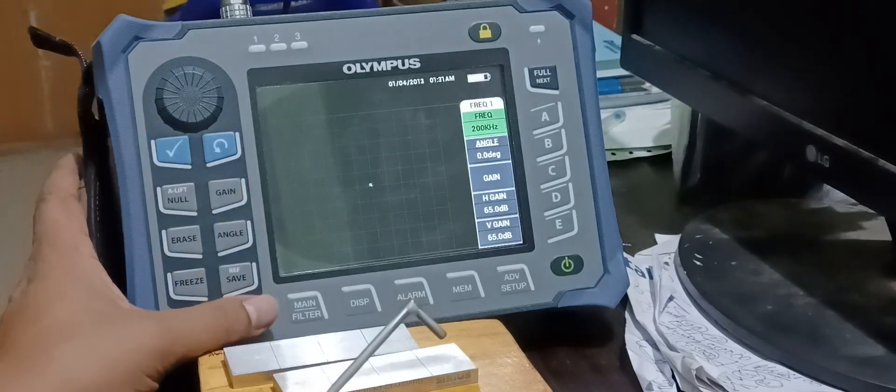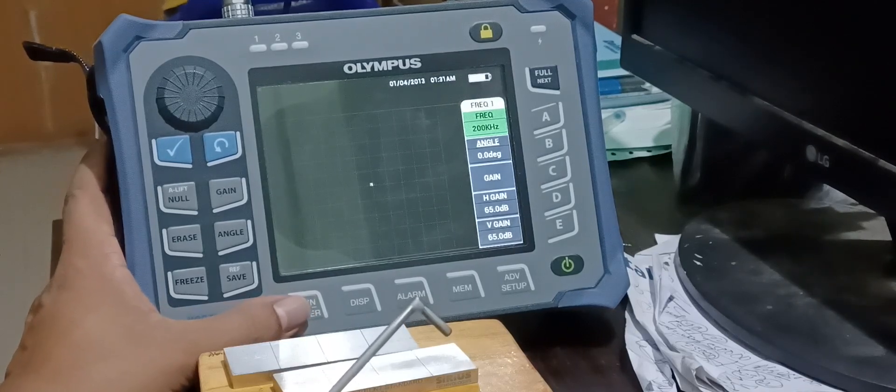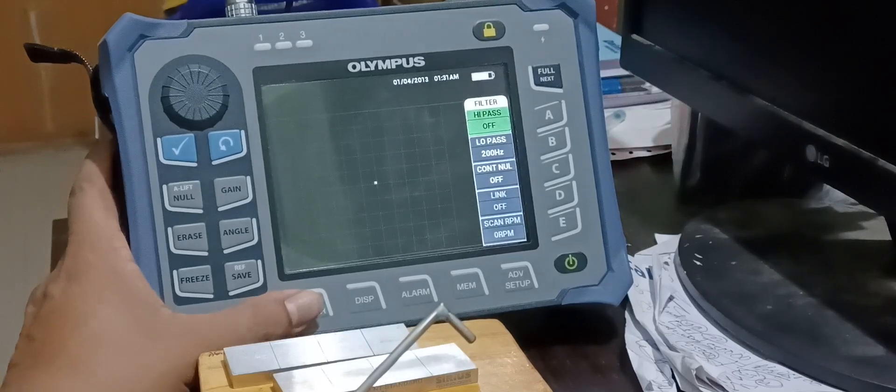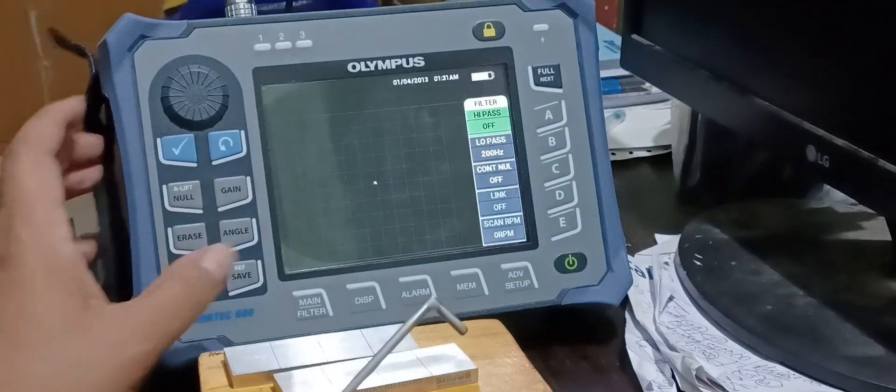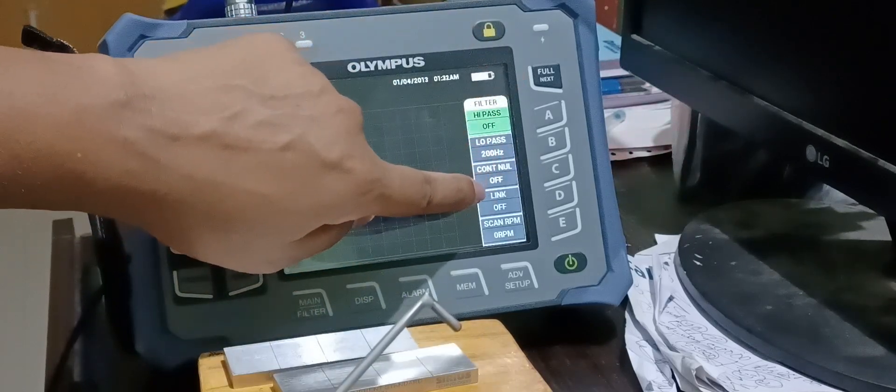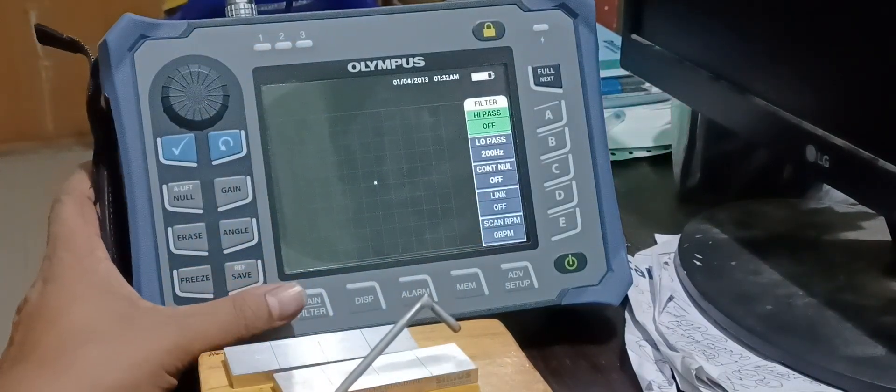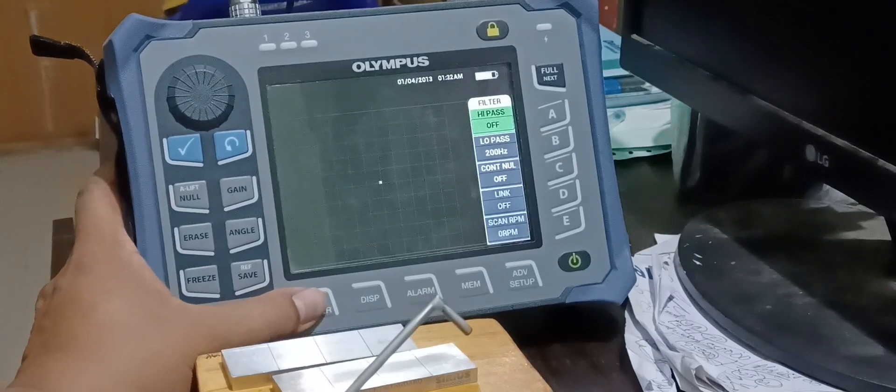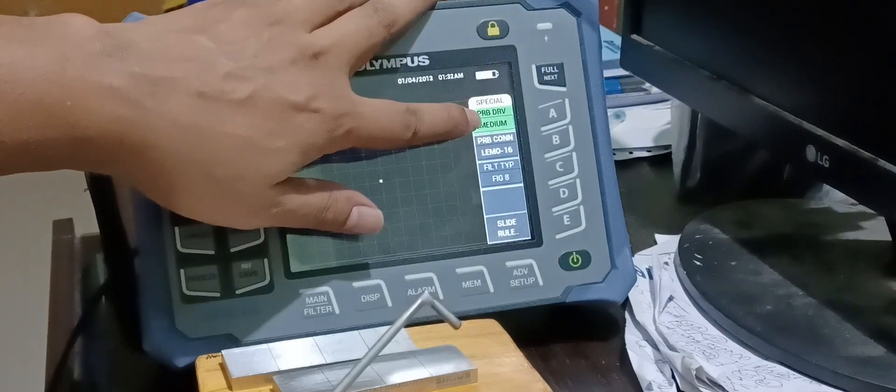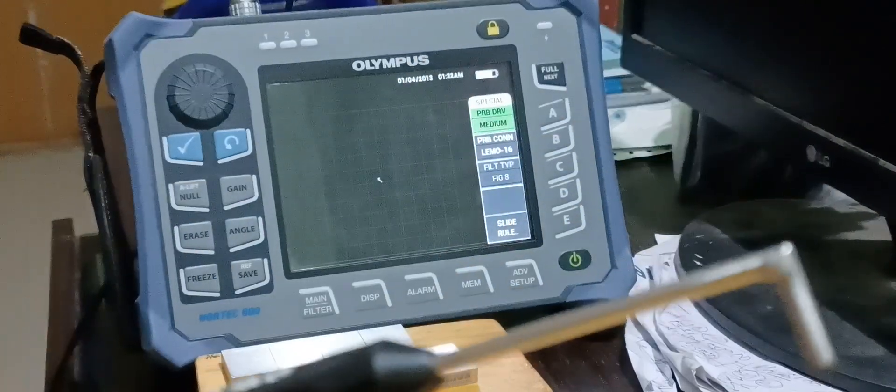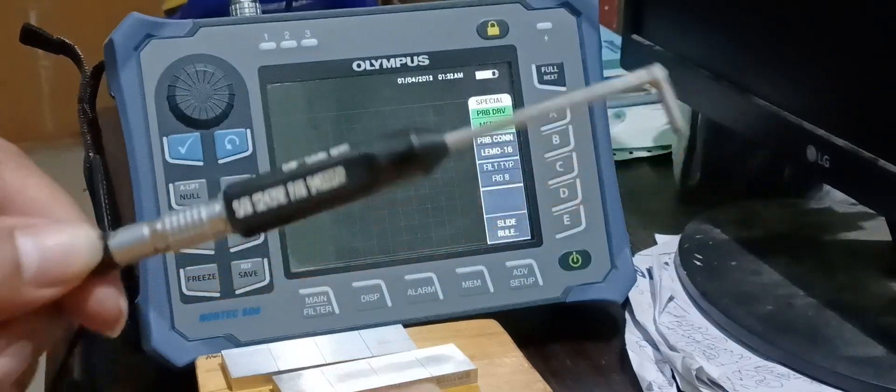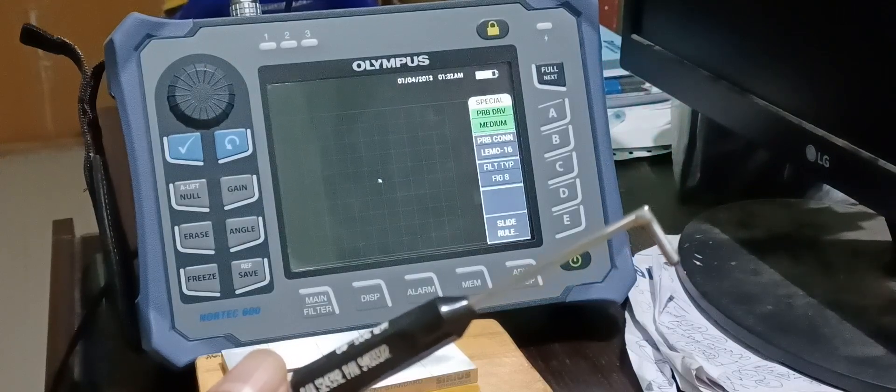You can go to different menus available in the down keys. For example, if I am pressing this main button, then I am going to the filter option, high pass, low pass and other options like continuous null. I am now taking it off. Link - I have not connected any kind of USB link or any data wire to the machine now. Scan RPM is only for when you connect a bolt hole probe or a miniaturized scanner. Now this is my probe drive. I am setting it in a medium drive. Probe connection is LEMO section. This whole thing is called a LEMO cable setting. Slide rule is to set the material and the standard depth.